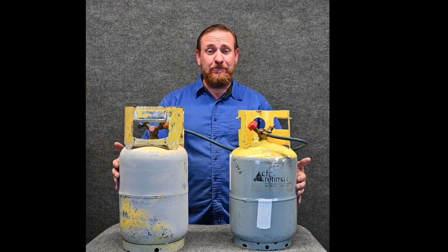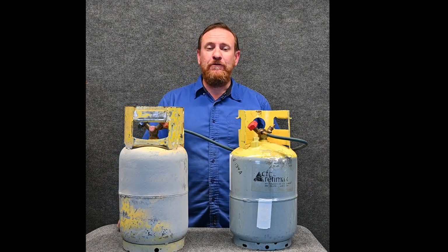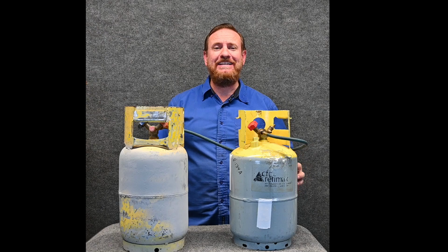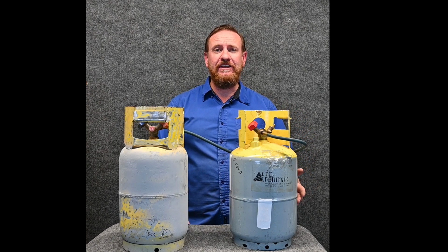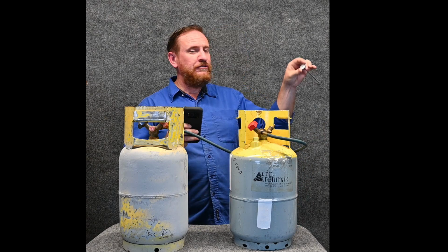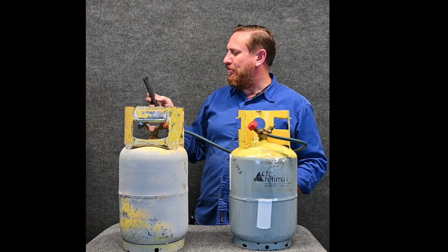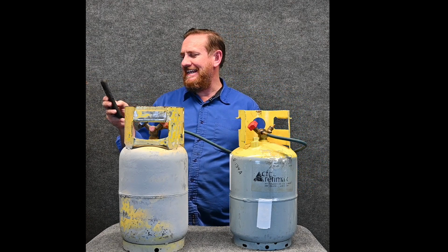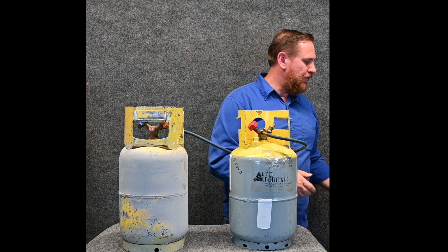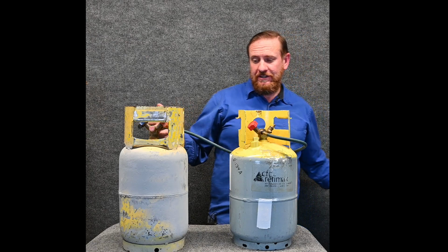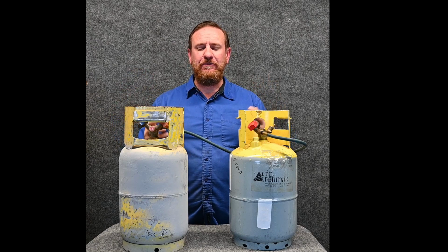It would be the same temperature. There's liquid and vapor. We know what the saturation is going to be. We could follow it. We could map it. If you want to try it, let's say this room temperature right now is about 95 degrees. So if we have 95 degrees and we know there's liquid and vapor with 410A, we can find out exactly what the pressure is going to be. So it's 95 degrees. If I had at least some liquid and vapor, that means the pressure would be about 299 psi gauge. So that's a significant amount of pressure, 299 psi gauge. So there would be no flow, the same pressure in both of these, nothing would happen.